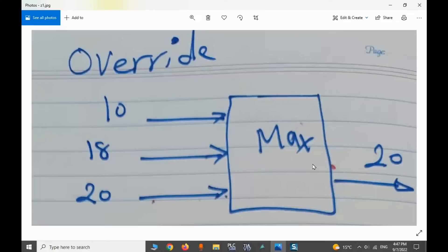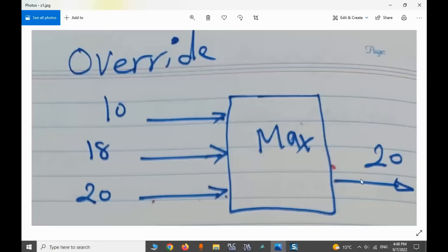In this example, we will have a maximum selector. We should develop a selector block. In our selector block, we have two inputs — we get the two inputs and generate the maximum. This selector can be used two times for three inputs: first we generate the maximum for the first two, and the output of the first max selector will be 18. Then we again select the max between 18 and 20, the last input.